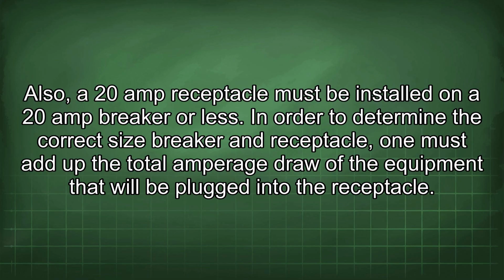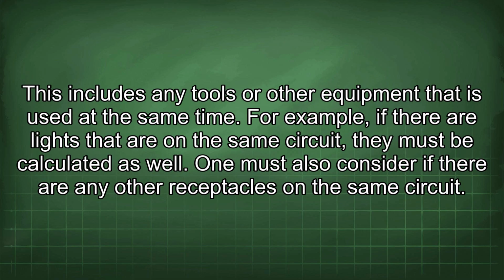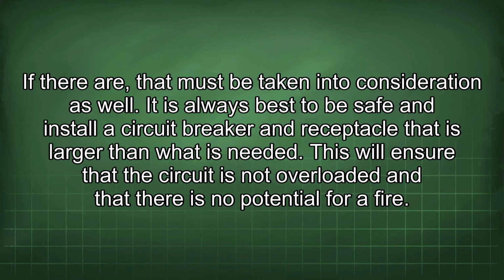In order to determine the correct size breaker and receptacle, one must add up the total amperage draw of the equipment that will be plugged into the receptacle. This includes any tools or other equipment that is used at the same time. For example, if there are lights on the same circuit, they must be calculated as well. One must also consider if there are any other receptacles in the same circuit. If there are, that must be taken into consideration as well.